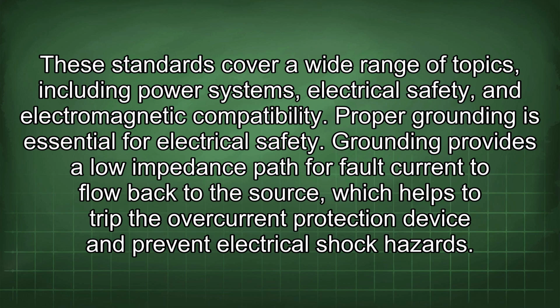Proper grounding is essential for electrical safety. Grounding provides a low impedance path for fault current to flow back to the source, which helps to trip the overcurrent protection device and prevent electrical shock hazard.